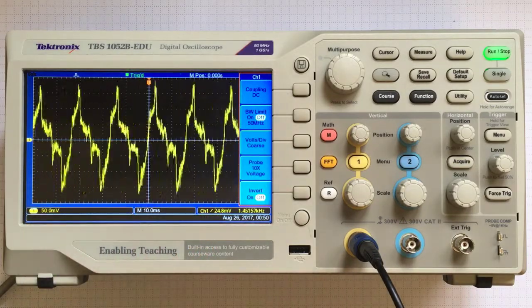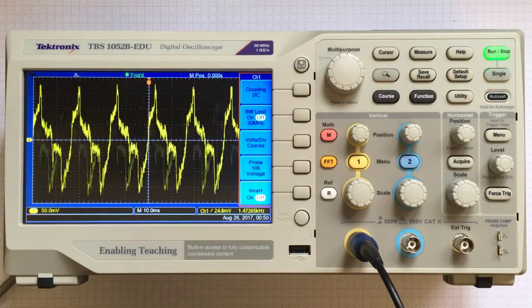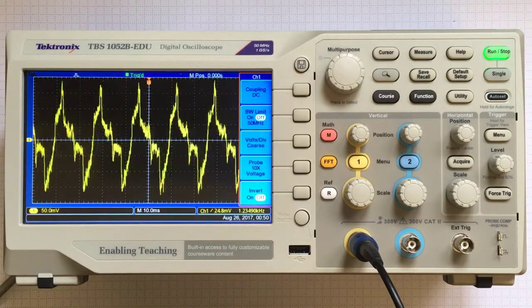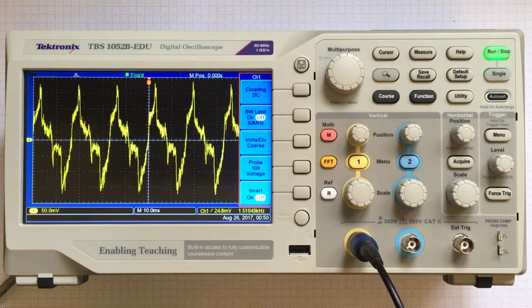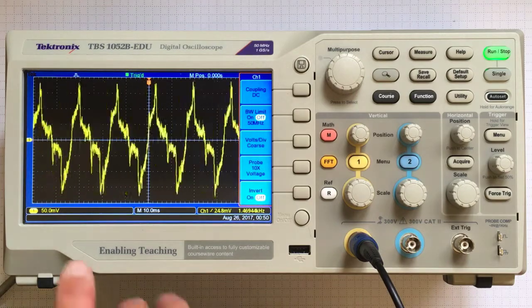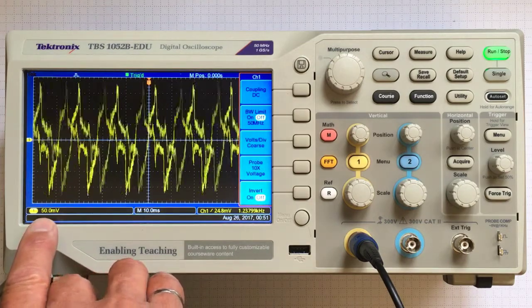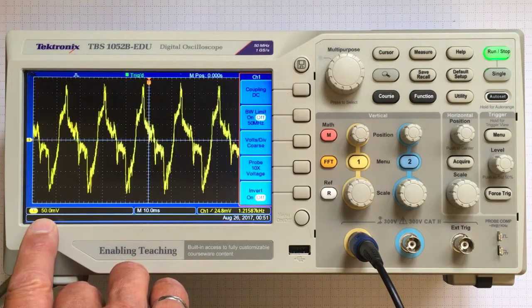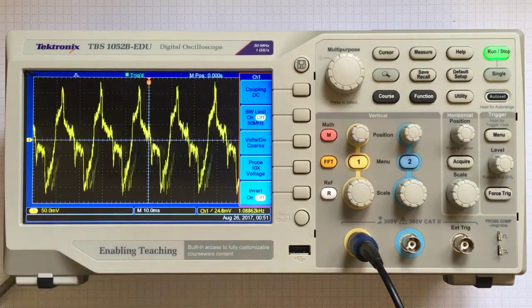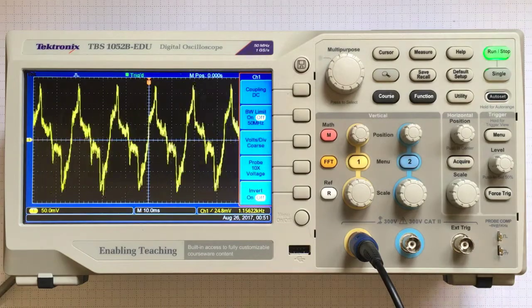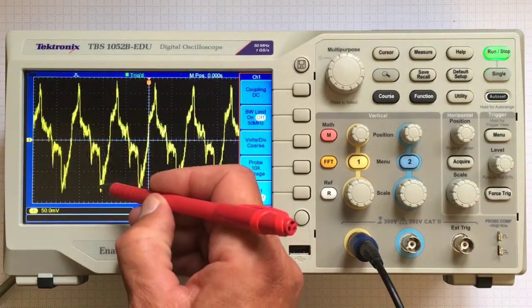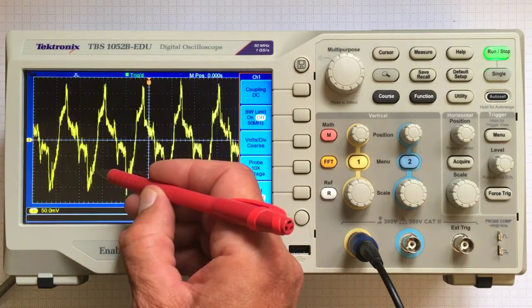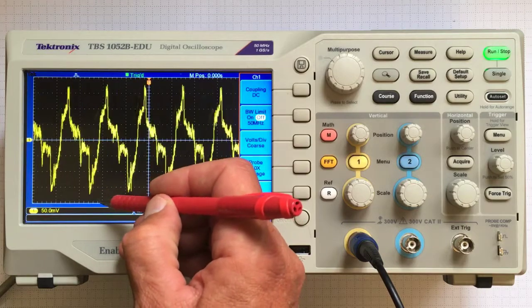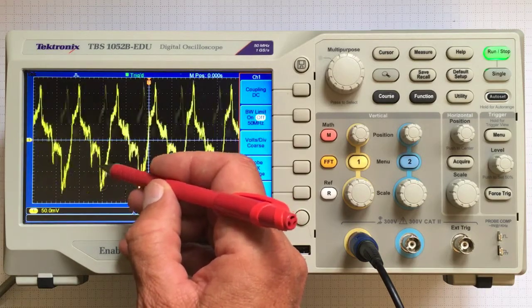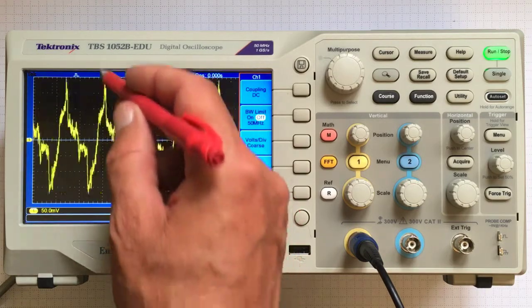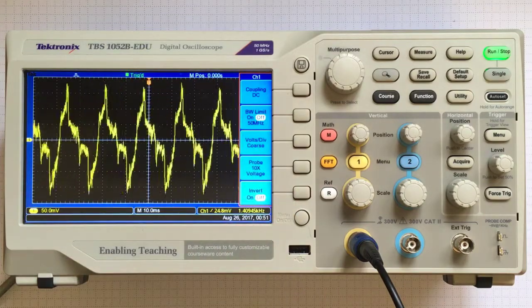This allows us to see what's going on much more quickly than if we used a multimeter and in much more detail. So there are a couple of things to notice here. Down here it says that we're on the 50 millivolt scale. That means that 50 millivolts is the voltage in between one of these dotted lines and the next dotted line. So the whole screen would be 50, 100, 150, 200, 400 millivolts tall.